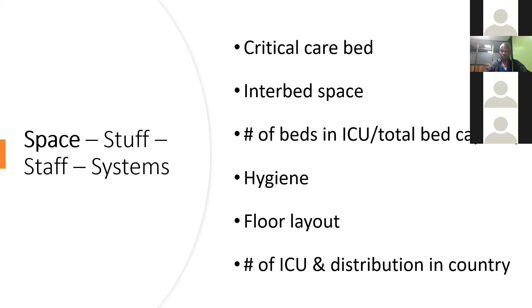A critical care bed, as some will call it, an ICU bed, is not just a bed, but a collection of items such as electrical functional bed, mattress, ventilator, suctioning machine, etc. There should also be provision for compressed gases and a minimum of about 6 socket plugs located at a height of between 120 and 180 centimeters from the floor. And now we're going to talk about equipment, consumables, and spare parts as stuff. Source of compressed medical oxygen and air is important for blending various FiO2s and for running pneumatic ventilators. This could be wall supply or cylinders. Remember, a backup cylinder or a concentrator is paramount.